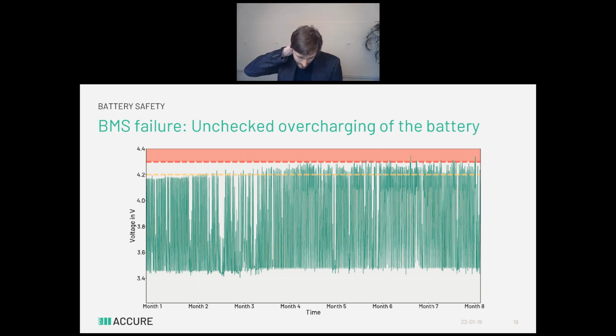Of course, it's not as simple as just comparing two values. You need to make sure all the values are cleaned properly, that systematic and random errors on the measurement are filtered out. You don't want to throw an alarm to the fire department every time your logger is rebooting. So there's actually quite some work needed to make a comparison like that, but from all of the analytics that we do, it's probably the simplest.